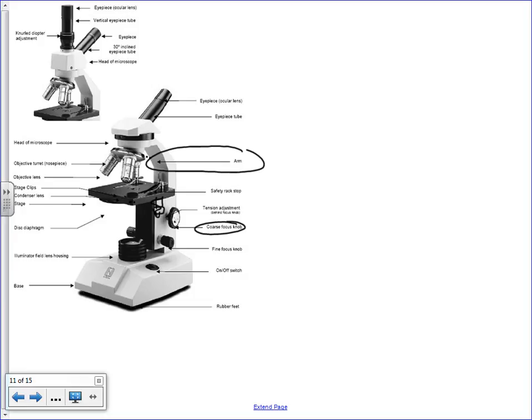Okay, if you're seeing stuff and when you move the slide, the stuff doesn't move with the slide, then it's something that's on the lens, and it's usually on this lens because that's the one that's closest to people's face. Things like eyelashes and stuff fall on there. If people are wearing mascara, I find that's the worst thing, because it comes off in little black clumps, and it's quite greasy, and it sticks to this, and then it smears on there.